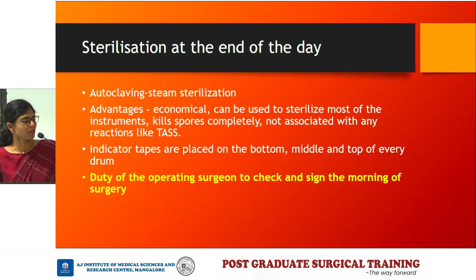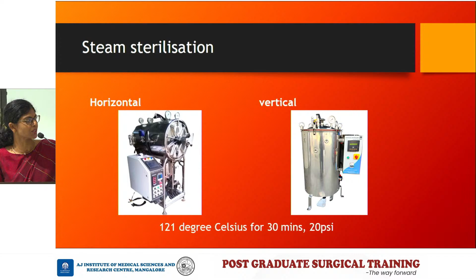So just for completion's sake, these are gravity-dependent autoclaves. Most of the OTs have these horizontal autoclaves or the vertical autoclaves. Basically, what is done is steam is pumped into the chamber, which will push the air out. So it takes some time for the air to completely come out. And then a temperature of around 121 degrees Celsius is achieved for about 30 minutes at 20 psi. So this is the usual steam sterilization that is done.